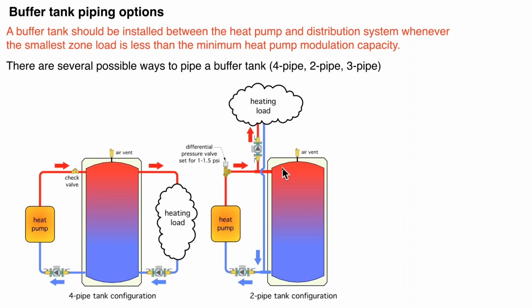The slower the flow going into the, I'll say the lower the volumetric flow rate going into the buffer tank, the less disturbance of temperature stratification in the tank. And temperature stratification is good. I've had people say, no, you want to fully mix that tank. That really, from a thermodynamic standpoint, is not ideal. It's not necessarily going to destroy the performance of the system, but from a pure thermodynamic standpoint, stratification of temperature in a buffer tank is actually beneficial.